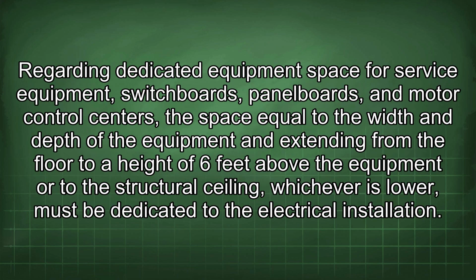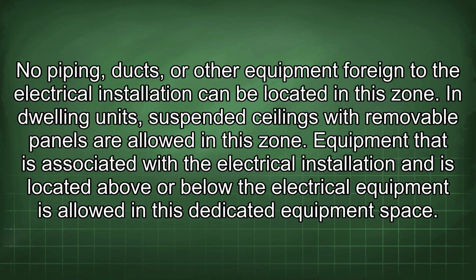Regarding dedicated equipment space for service equipment, switchboards, panelboards, and motor control centers, the space equal to the width and depth of the equipment and extending from the floor to a height of 6 feet above the equipment or to the structural ceiling, whichever is lower, must be dedicated to the electrical installation. No piping, ducts, or other equipment foreign to the electrical installation can be located in this zone. In dwelling units, suspended ceilings with removable panels are allowed in this zone.